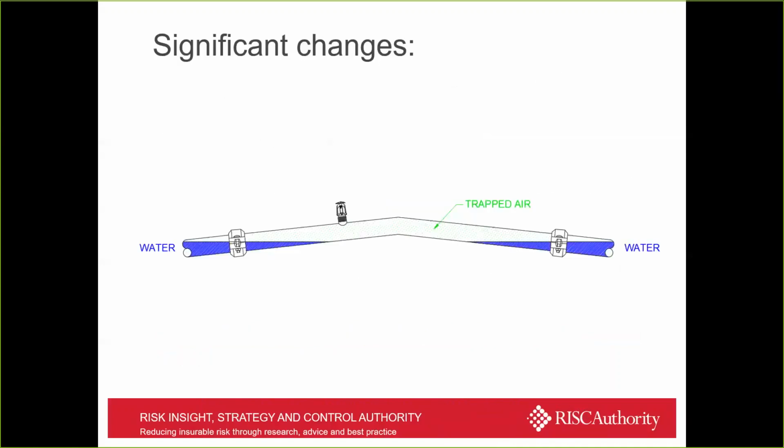So just going back to the air venting situation. This is particularly important for gridded systems. We're looking at a typical sectional view through a range pipe on, say, a warehouse where it goes up and over the roof, and that's the position at the apex. So all those range pipes on a gridded system will undoubtedly have air in the top section of them.